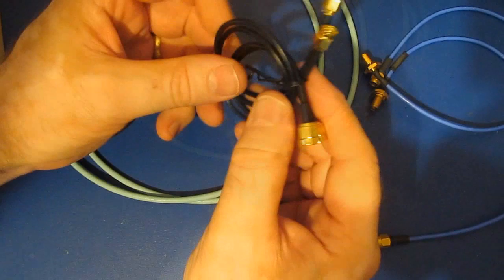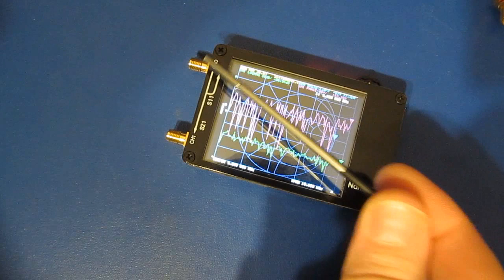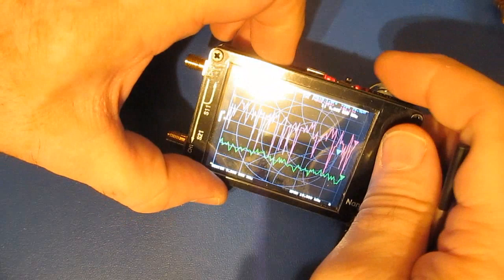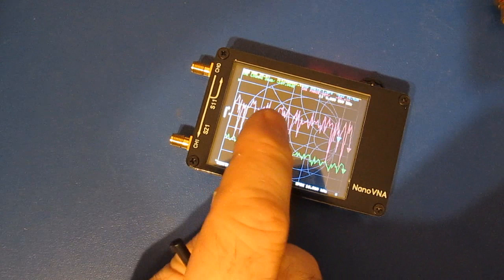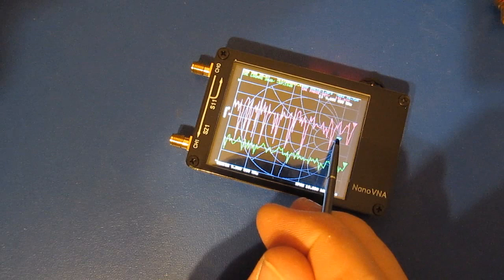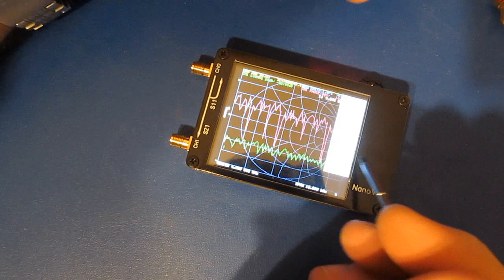For our initial testing I'm just going to go ahead and use what was supplied with the unit. This stylus came with a PDA — I find it works much better than trying to use the selector switch to control the unit. It's just a touch screen; you can select with your finger, but moving the cursor doesn't work very well with a finger. Let's go ahead and run a calibration.